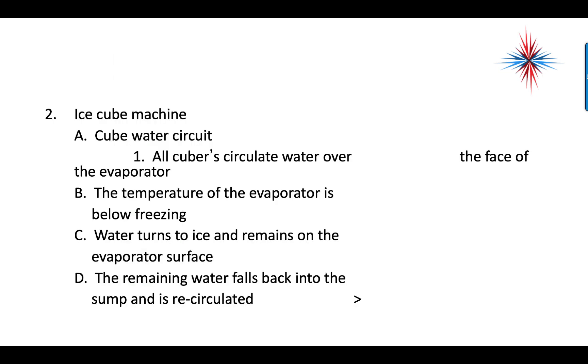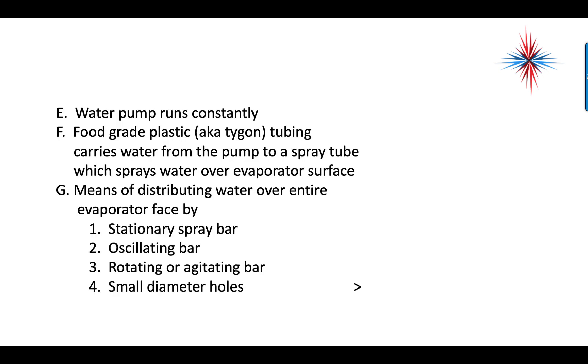The ice machine cuber water circuit - all cubers circulate water over the evaporator. The temperature of the evaporator is below freezing. Water turns to ice and remains on the evaporator's surface. The remaining water falls back into the sump and is recirculated. Water pumps run constantly. Food-grade plastic tubing carries the water from the pump to a spray tube, which sprays water over the evaporator surface.